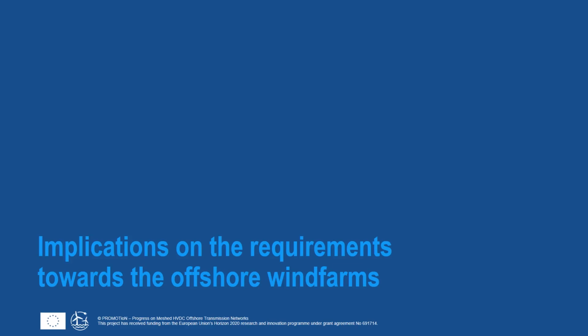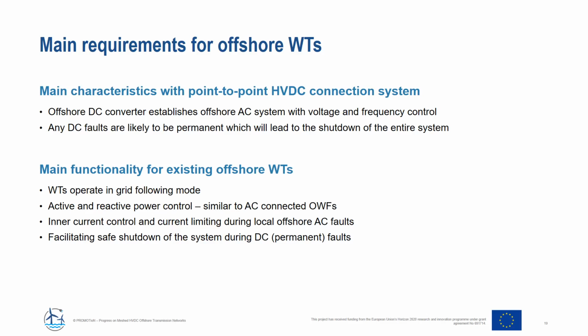In this part, the implications on the requirements towards the offshore wind farms, considering different DC protection strategies, are investigated. Start from the existing point-to-point HVDC connection system. In such a system, the offshore DC converter establishes the offshore AC system with voltage and frequency control, and any DC faults are likely to be permanent, which will lead to the shutdown of the entire system. So existing offshore wind turbines usually operate in grid following mode. The active and reactive power are controlled in a similar way to AC connected offshore wind farms. There will be inner current control and current limiting capability during local offshore AC faults. In the event of DC fault, the main requirement is to facilitate safe shutdown of the system.